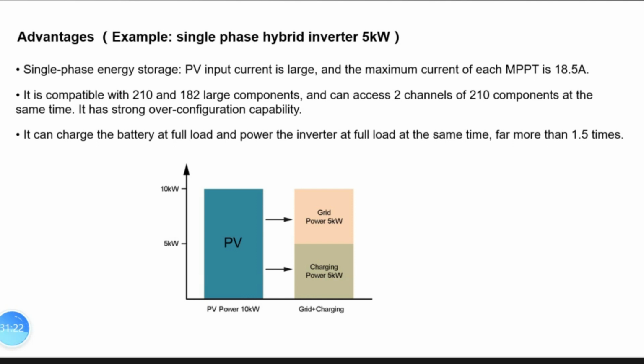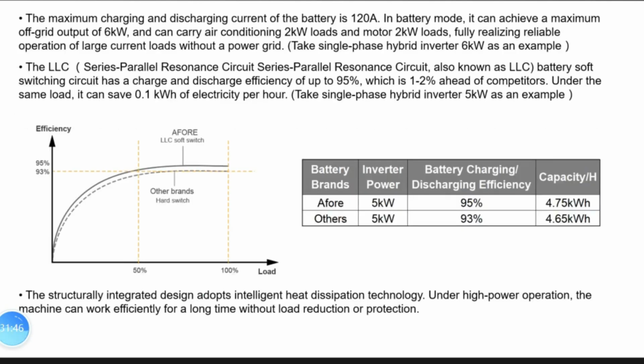so if the PV delivers more power, the inverter can deliver more power to the load, and in the meantime deliver more power to charge the batteries at the same time. So here is a picture of examples for the 6K single phase 1 plus version. They have more capacity to deliver energy under the EPS mode, and compared with other brands, the plus version can connect some big loads like an air conditioning motor. For the 6K, it can power 2 kilowatt air conditioning and also 2 kilowatt motors.